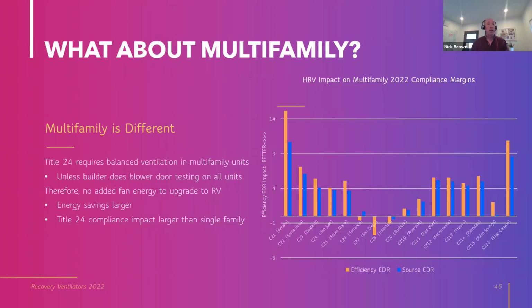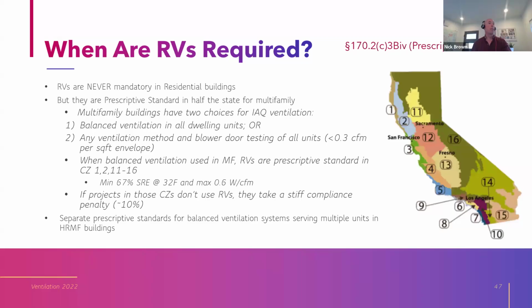Okay, but if you do use balanced ventilation, the standard design also has balanced ventilation. So there's no added fan energy penalty in the multifamily world. So the energy savings are larger and the compliance impact's larger, as you can see in this chart. Although you see the same climate zones performing worse and the same climate zones performing better. So also a really nice boost to multifamily.